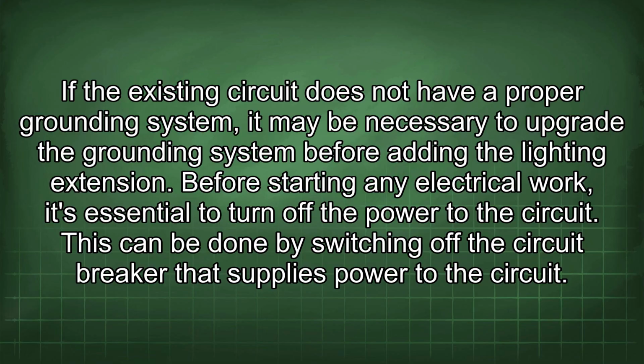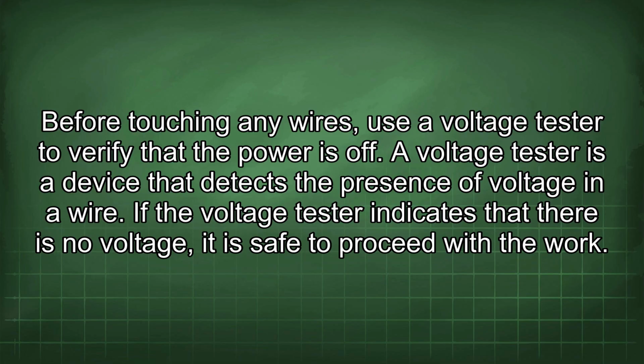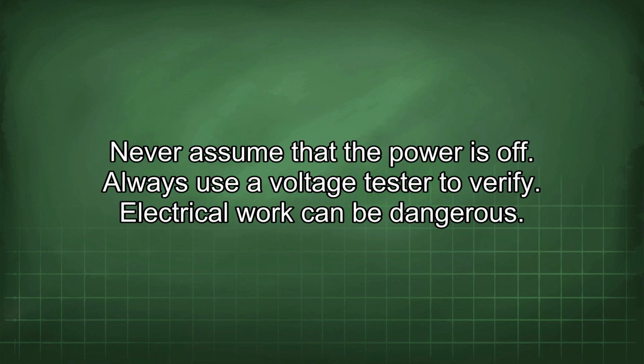Before starting any electrical work, it's essential to turn off the power to the circuit. This can be done by switching off the circuit breaker that supplies power to the circuit. Before touching any wires, use a voltage tester to verify that the power is off. A voltage tester is a device that detects the presence of voltage in a wire. If the voltage tester indicates that there is no voltage, it is safe to proceed with the work. Never assume that the power is off. Always use a voltage tester to verify.